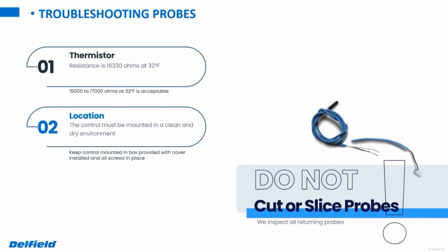Again, not all ice water is created equal, so we're not normally going to hit that 16,330 exactly at 32 degrees. So again, if you fall in that 15 to 17K ohms, then they're normally in good shape. But again, the go-to is going to be doing that real-time probe reading. So that's why I want you to check out that video and familiarize yourself with it, because that is something that we'll have you do in most instances.